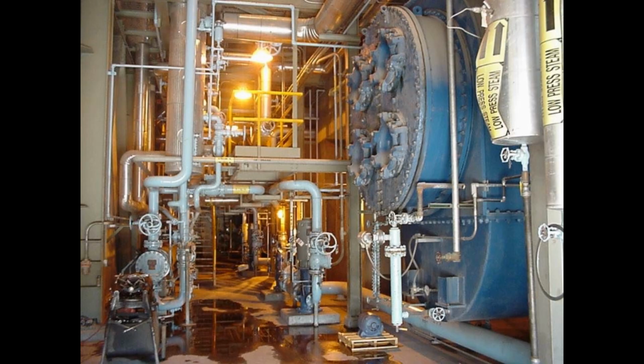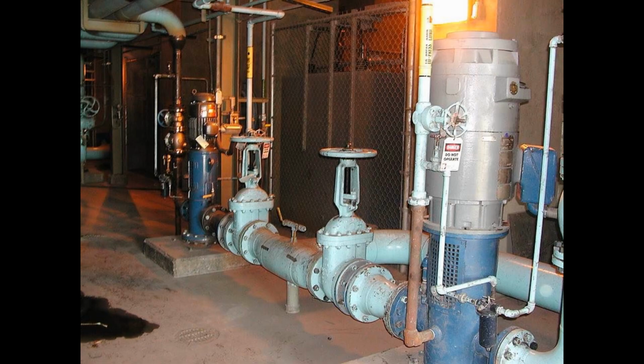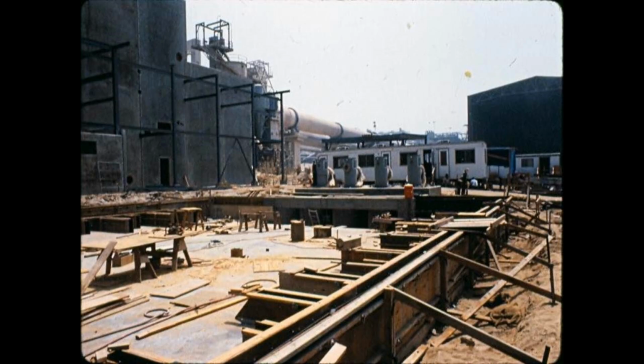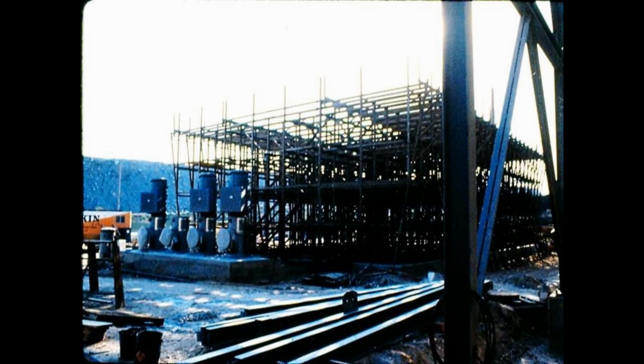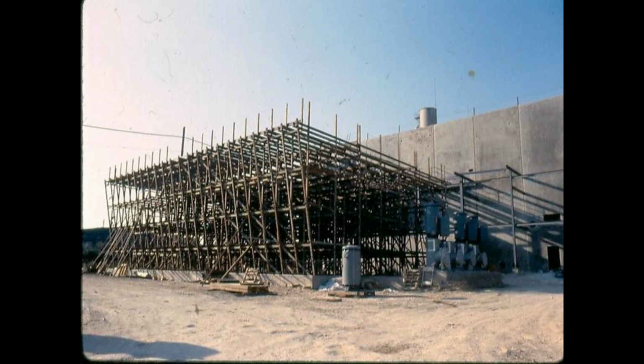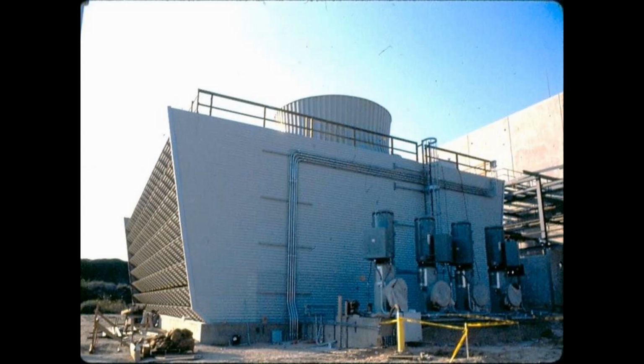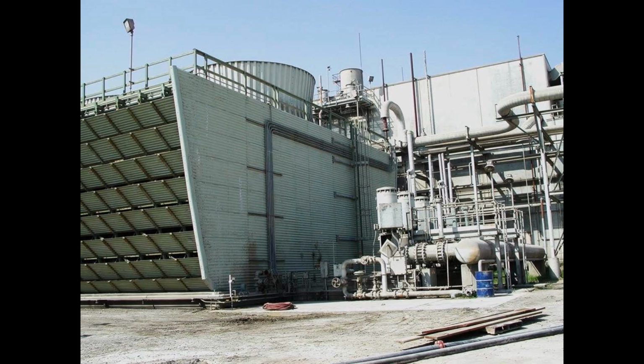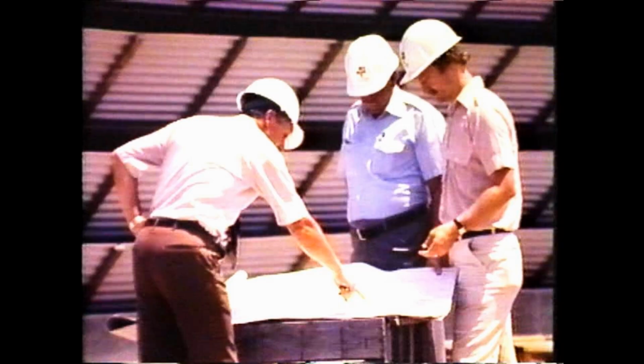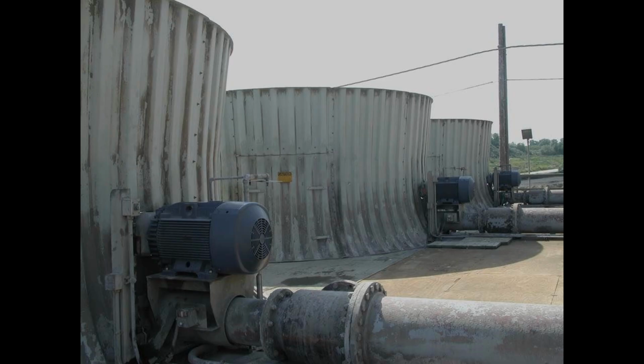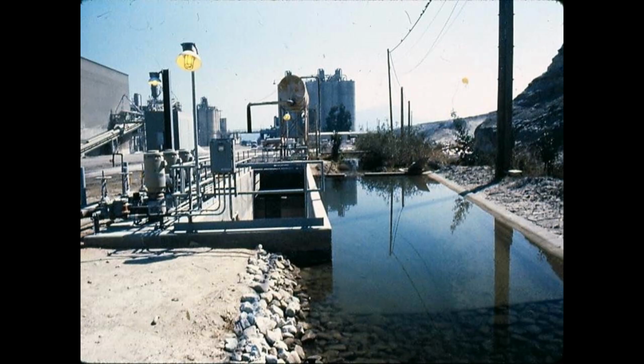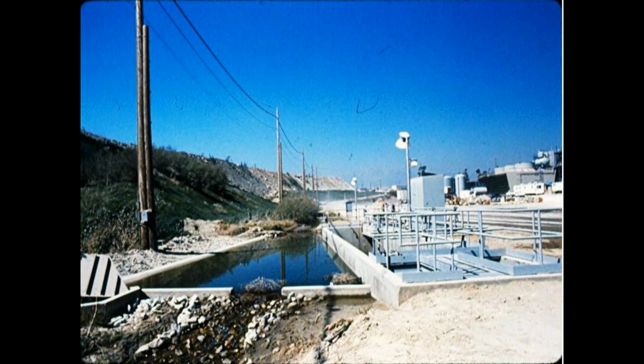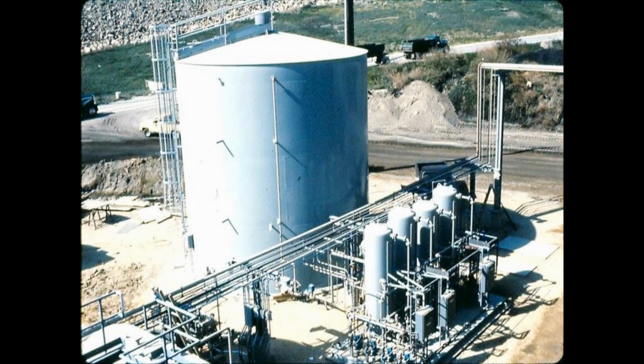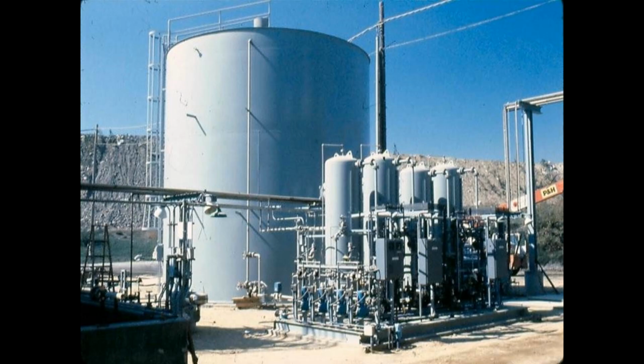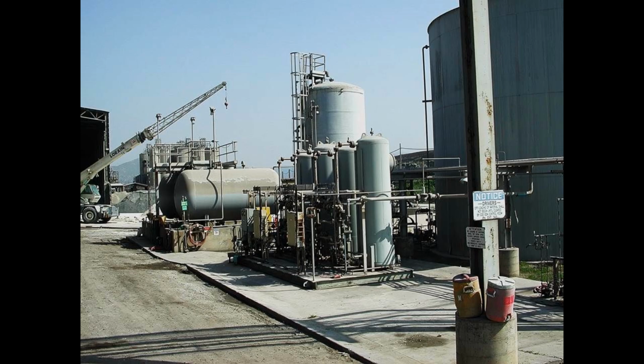Water used in the cement plant is primarily for non-polluting uses. This water, after a small amount of heat is added, is usually discharged into an open area and allowed to evaporate. The cogeneration project reclaims this once-used water and passes it through a settling basin where solids are removed. The water is then used for cooling tower water makeup. The boiler water lost through blowdown is replaced with demineralized water produced in a mixed bed multi-train demineralizer. This water then contains less than 5 parts per million total dissolved solids.